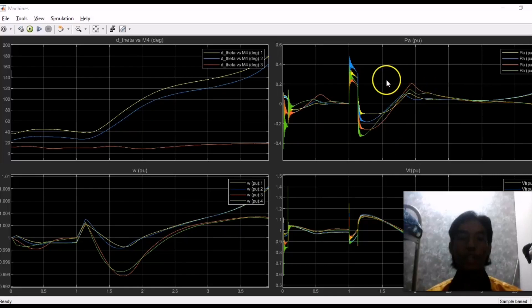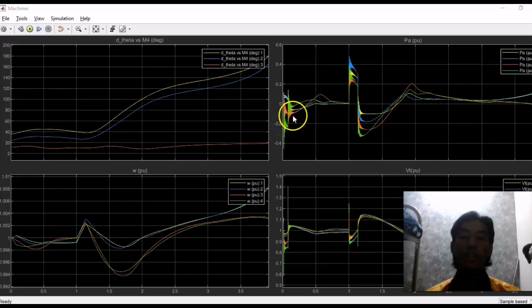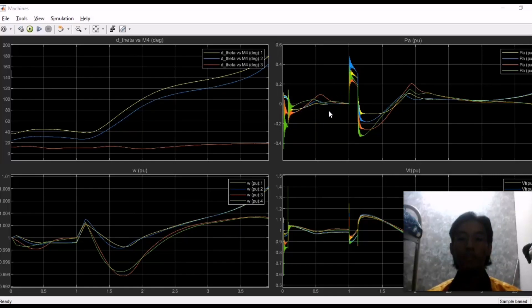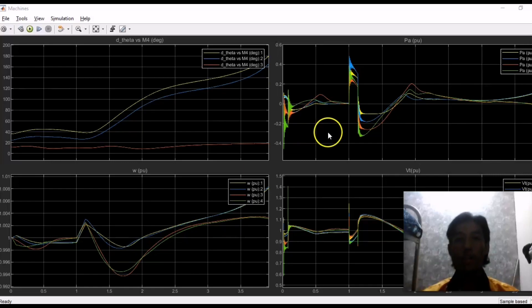For the electrical power versus time graph, the green and red represent generator 3 and generator 4 at area 2, while the blue and yellow represent generator 1 and 2 at area 1. The rise of area 2 was significant compared to area 1 due to the load increment. After 150% of load increment, the electrical power consumed by generator 3 and generator 4 is 2.2 per unit, and synchronism stops when the load increment reaches 150%.